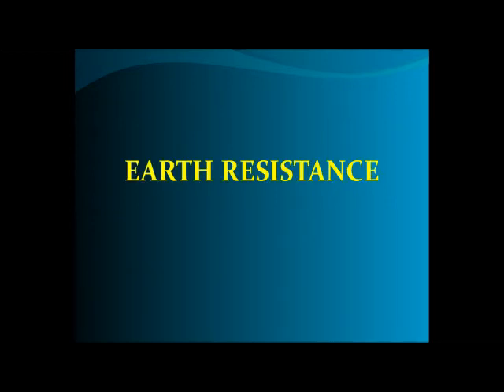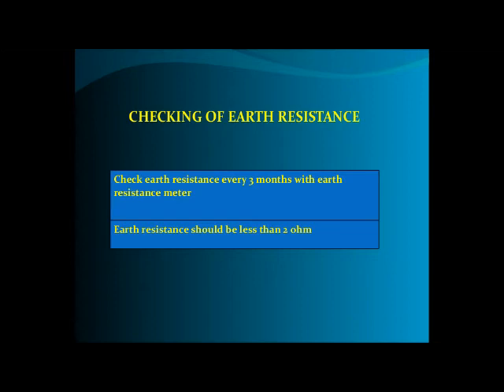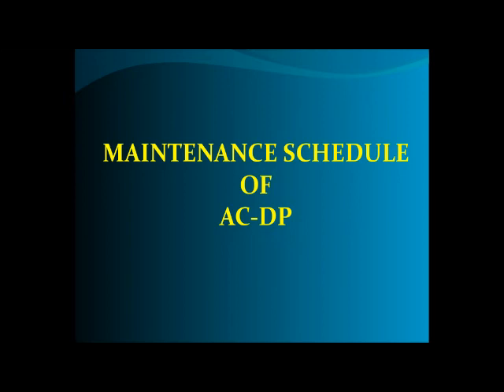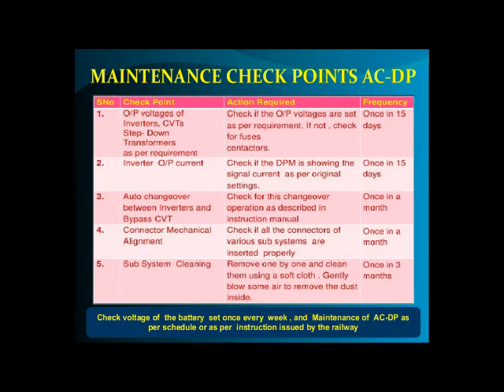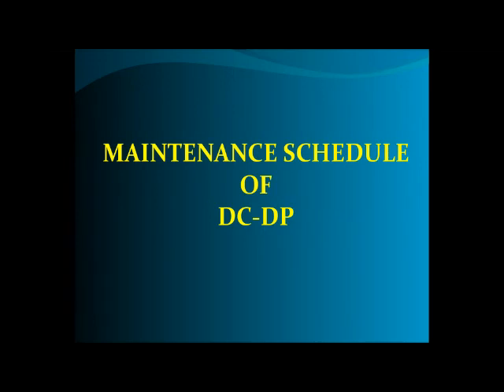Earth resistance: Check earth resistance every 3 months with an earth resistance meter — it should be less than 2 ohm. Maintenance schedule of AC Distribution Panel (ACDP) and maintenance schedule of DC Distribution Panel (DCDP) are to be followed as specified.